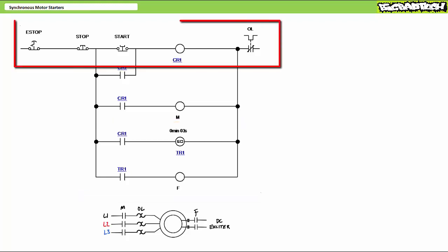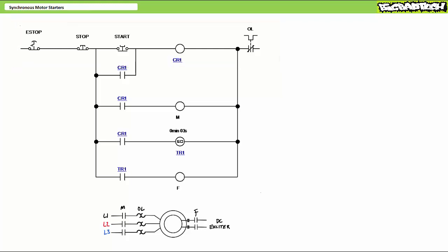Rung one consists of the series combination of a normally closed E-stop, a normally closed stop, a normally open start, the coil of control relay CR1, and a normally closed thermal overload. All the normally closed devices serve to de-energize CR1 in the event of an operator-initiated stop, an emergency, or a sustained overload. An operator can start the system by pressing and releasing start, which energizes the coil of CR1.